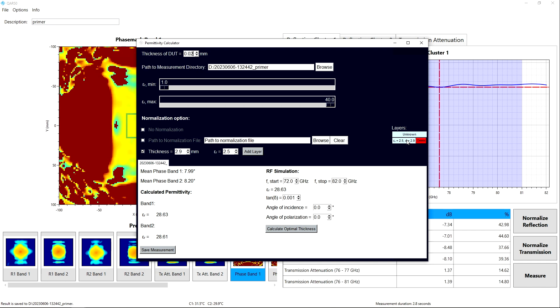The polypropylene plate used for normalization has a thickness of 2.9 millimeters and a permittivity epsilon r of 2.5 — this layer has been added in the software as shown. The software then tells us that, given the thickness of the primer, its estimated permittivity is 28.6. Since the permittivity calculation is highly dependent on the thickness of the part, it is extremely important to measure the thickness of each layer with the highest precision possible.